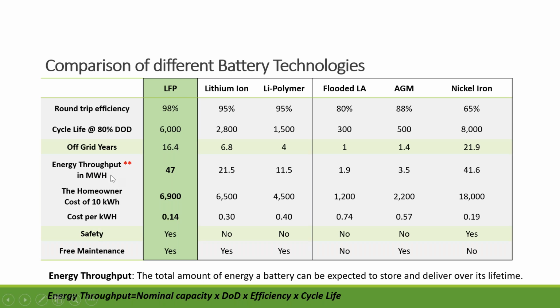Energy throughput in megawatt hours, that's something I want to explain to you, how this number is calculated. You take your nominal capacity, multiply by your depth of discharge, multiply by your efficiency, and multiply by your cycle life. So in this case, take a 10 kilowatt hour battery bank. 10 kilowatt hours multiplied by 80%, multiplied by 98%, and multiplied by 6,000 cycles, you can expect 47 megawatt hours of energy from the battery's lifespan. The other two lithium batteries are substantially less, and of course flooded AGM is much, much less. Nickel iron is at a similar level.